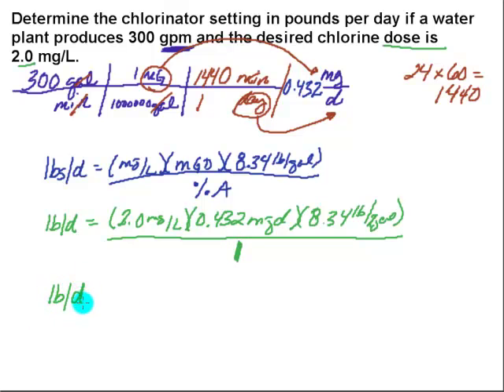So any time they don't give you a percent available or it says chlorine gas, this number is going to be a 1. So everything above the line gets multiplied. So I've got 2 milligrams per liter times my 0.432 times 8.34, and it looks like about 7.2 pounds per day is where the chlorinator setting should be set.